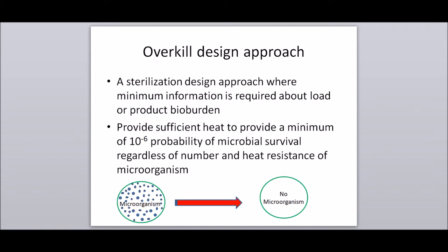Overkill Design Approach: a sterilization design approach where minimum information is required about the load or product. It provides sufficient heat to deliver a minimum probability of microbial survival of 10 raised to minus 6, or delivered lethality, regardless of the number and heat resistance of microorganisms.